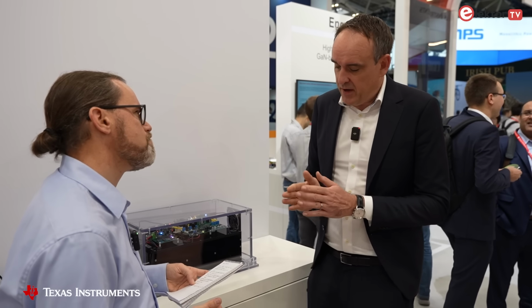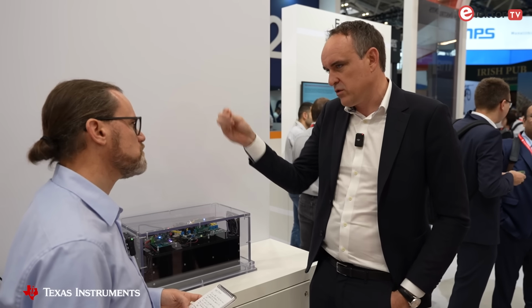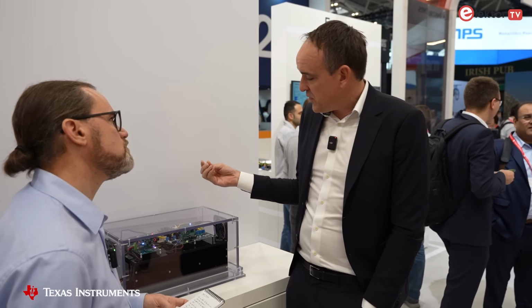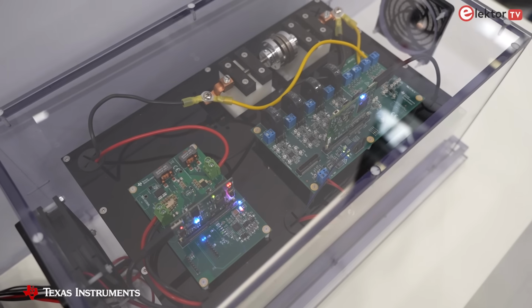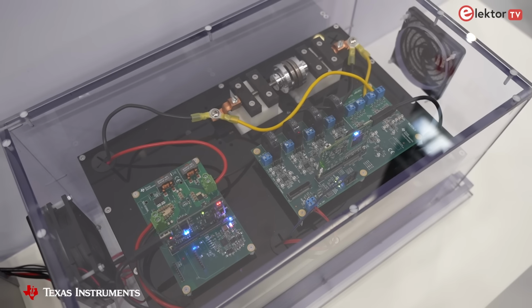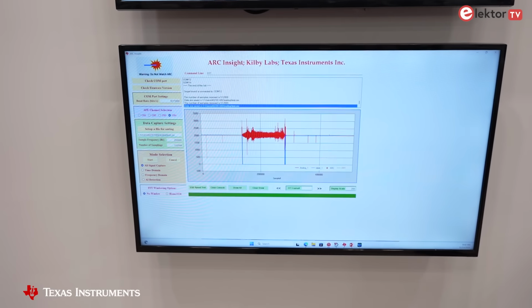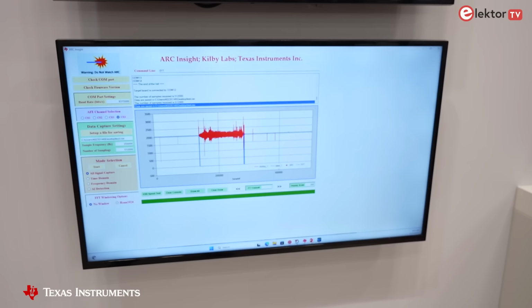So, if we think about that, we get that high voltage, high current line coming into the string inverter, and what we try to do there is put a system in place to measure the arcs, and we do that usually through some kind of current transformer that looks at the current, because an arc is usually going to show up as some kind of broadband noise pattern atop of this DC line in the system. And most traditional systems today are built on an FFT method.